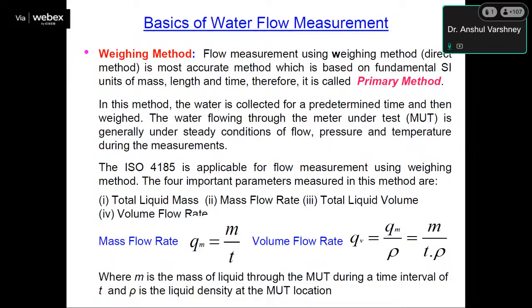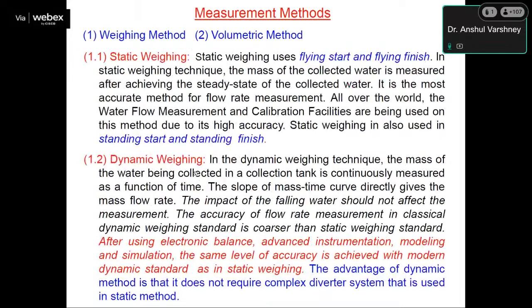So I earlier told how we are calculating the mass flow rate. Basically, in the weighing method, mass flow rate is mass divided by time. Volume flow rate is basically mass flow rate divided by density at that particular temperature. There are two types of measurement methods: weighing method and volumetric method. In the weighing method, there are two types of weighing: static weighing and dynamic weighing.